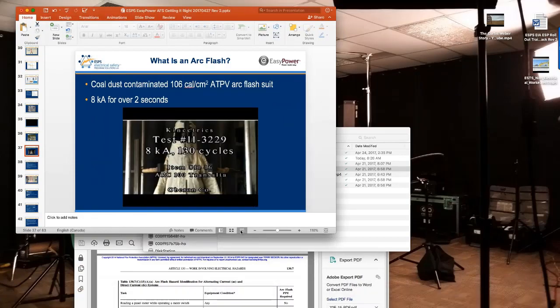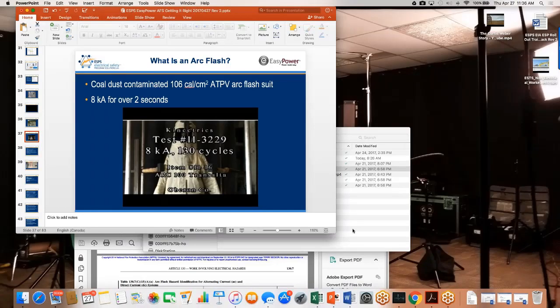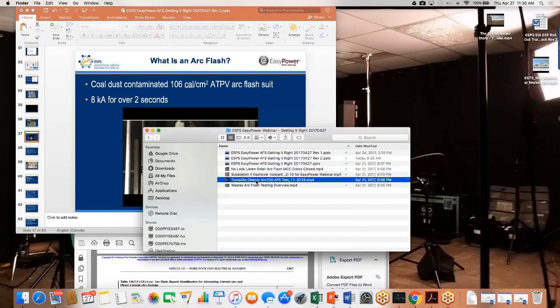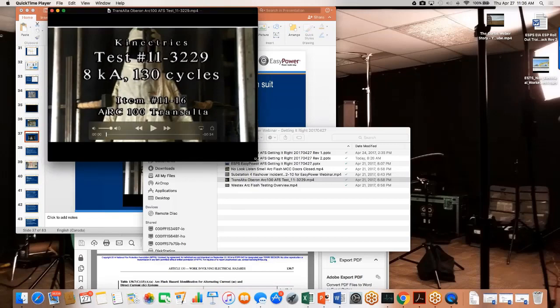This last video is about contamination of PPE. The arc flash suit that you're going to see is an Oberon Arc 100 or 106 cal suit. I was able to work with a client on a large coal-fired power plant, TransAlta Corporation, and they allow me to use this video. This was a coal-infused arc flash suit.